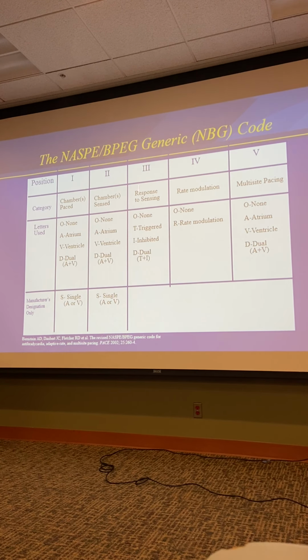Sensing, it's a simple concept, but it's often misunderstood. So the P waves have a certain amplitude in millivolts. The R waves have a certain amplitude in millivolts. And we adjust what's called the sensitivity, and some people feel like the idea of sensitivity works backwards, but it doesn't. The higher you make the number, the less sensitive it is. So if you set the sensitivity at 5 millivolts, it means it's only going to see things that are higher than 5 millivolts. If you set the signal at 2 millivolts, you'll see things that are higher than 2 millivolts. So as you make the number go down, you see more and more of the signal.